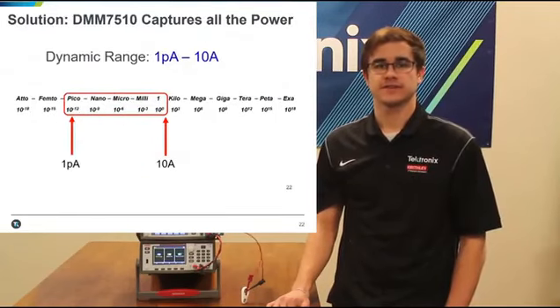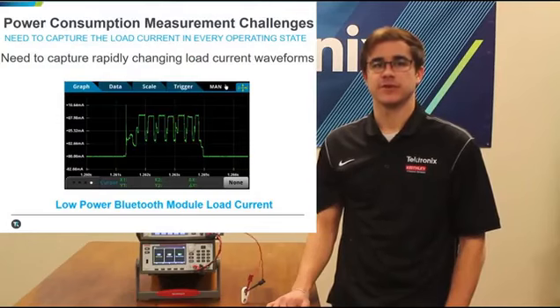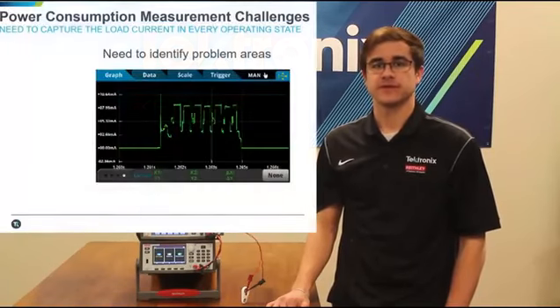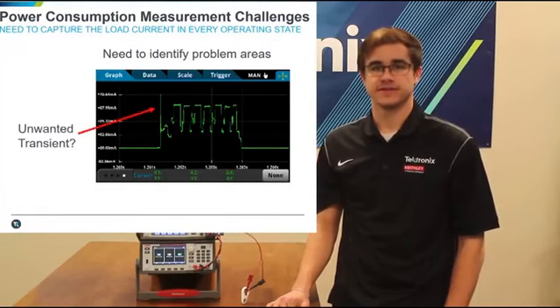Another challenge in capturing current characteristics of these devices is the speed that they change states, some only lasting tens of microseconds. We will need an instrument capable of capturing rapidly changing load current waveforms. Because the 7510 has a sample rate of up to a million samples per second, a very clear and detailed waveform can be found, exposing the current profile and allowing you to identify any power wasting problem areas such as unwanted transients.